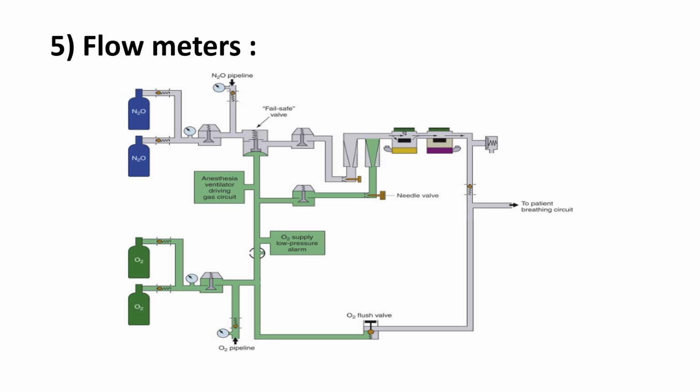and the final pathway of oxygen inside the anesthesia machine is through the flowmeter, which is separating the high flow circuit from the low flow oxygen circuit, the 35 to 50 psi from the 14 psi for oxygen and 26 psi of nitrous through this flowmeter.